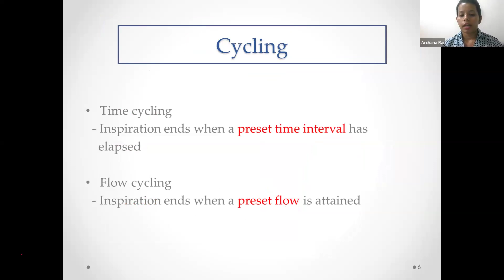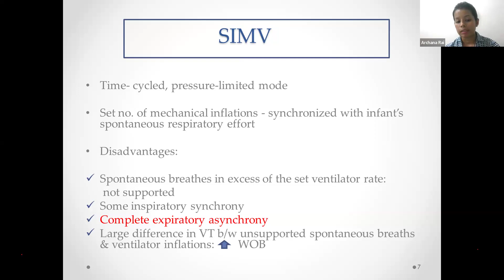So as our talk is first on the SIMV mode combined with the PSV mode, I just want to have a brief review of the SIMV mode. This is a time cycled mode, and it is a pressure limited mode. In this, the set number of mechanical inflations will be given, which will be synchronized with the infant's respiratory effort. The disadvantage is that the breaths in excess of the set inflations will not be supported. So there will be some inspiratory synchrony, but there will not be complete expiratory synchrony. And also there will be a difference in the tidal volume achieved between the supported and the unsupported breaths. Therefore, there will be more work of breathing.